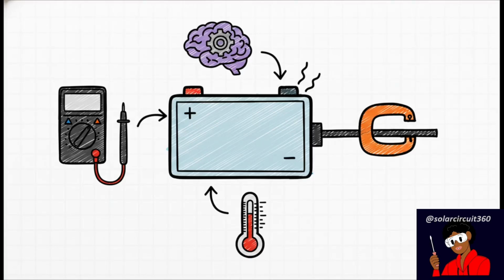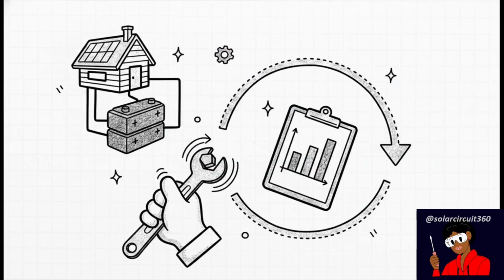Now, before we deploy this unit to power your off-grid life, we have to hit a few critical test targets. You need to validate the total and individual cell voltages and double-check that BMS operational logic. You're also going to want to use a clamp meter to validate the current flow. If you haven't used one before, a clamp meter is this brilliant tool that lets you measure the invisible flow of electricity just by clipping its jaws right around the outside of the wire. You don't even have to break the circuit. During your initial charge and those moderate load tests, you'll want to actively monitor the physical battery for warm connections. Remember, heat is an early warning sign of excessive electrical resistance, usually from a poorly torqued joint. Once your battery passes those tests, it is officially ready for the wild.